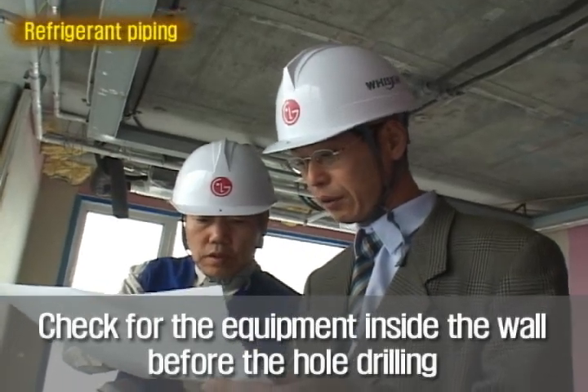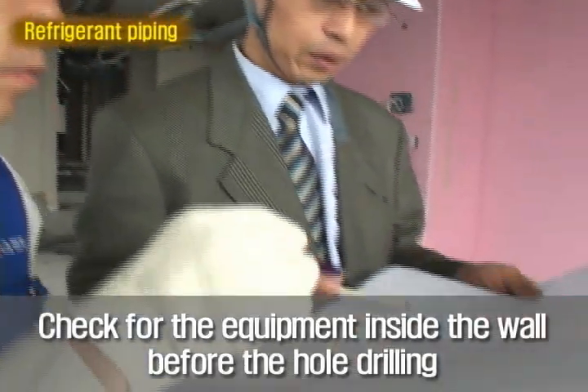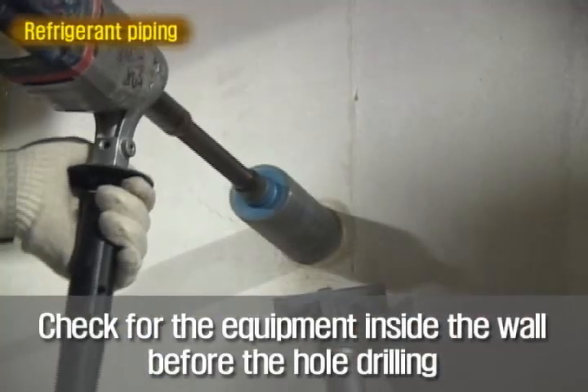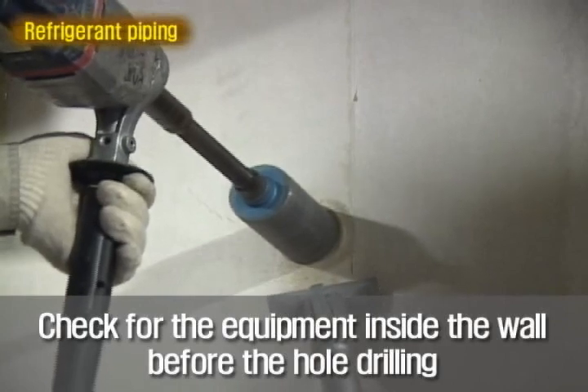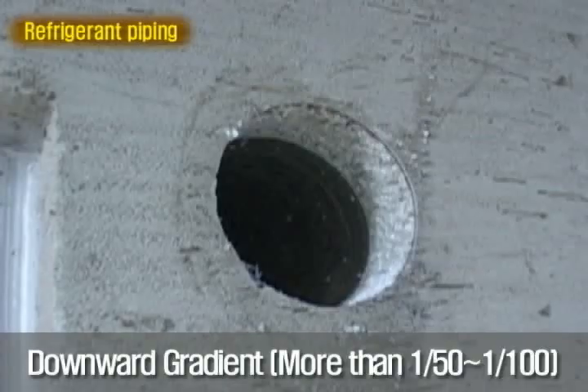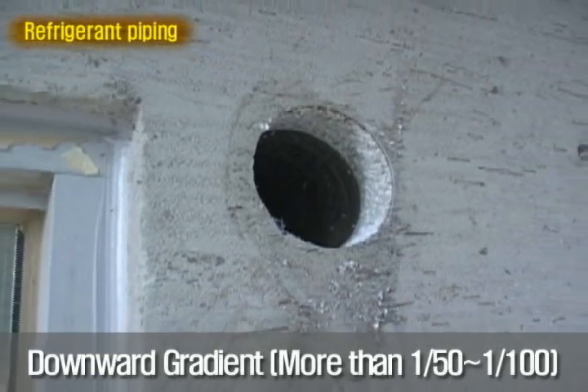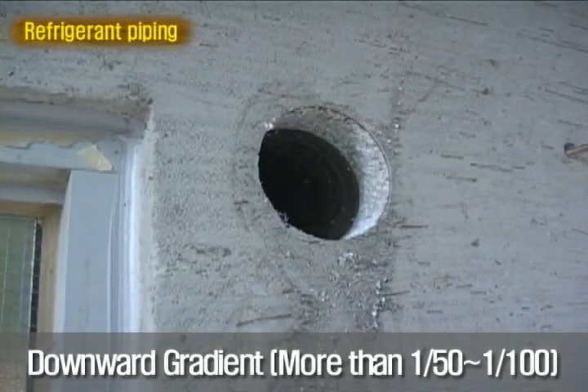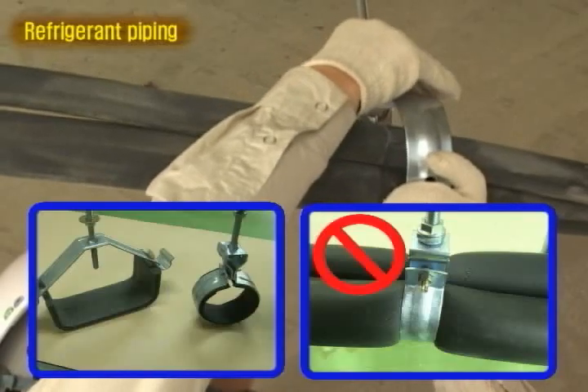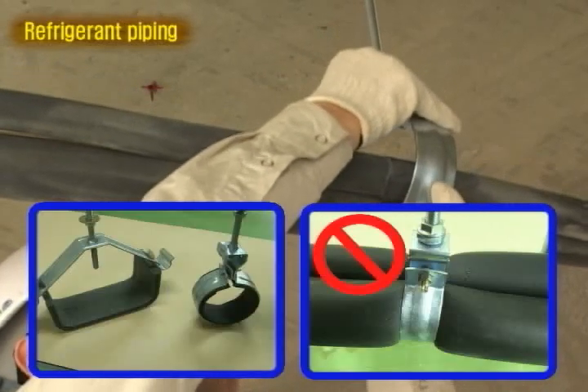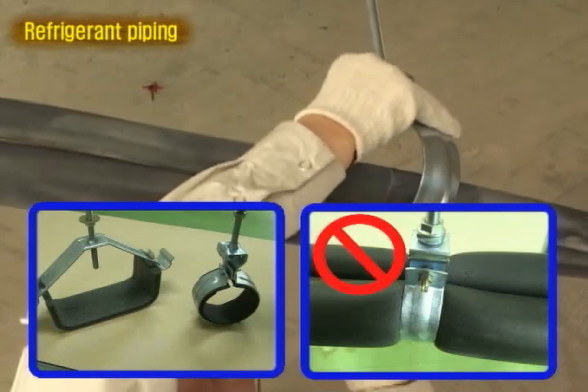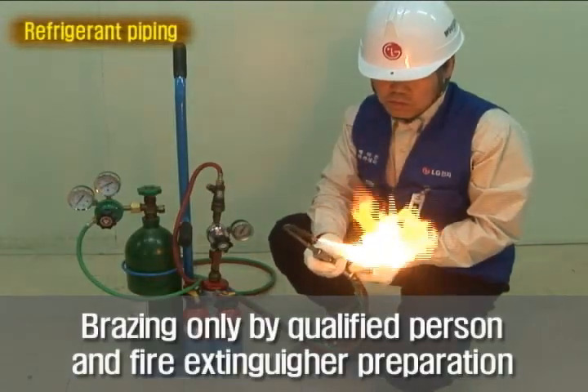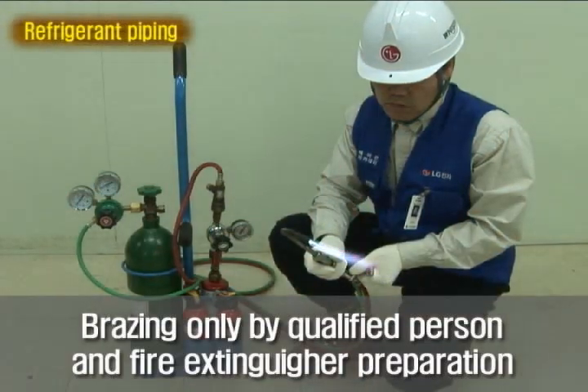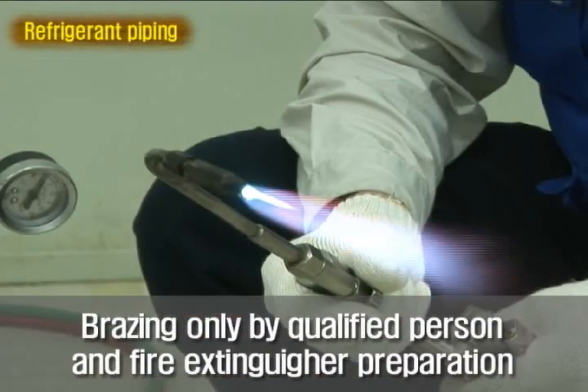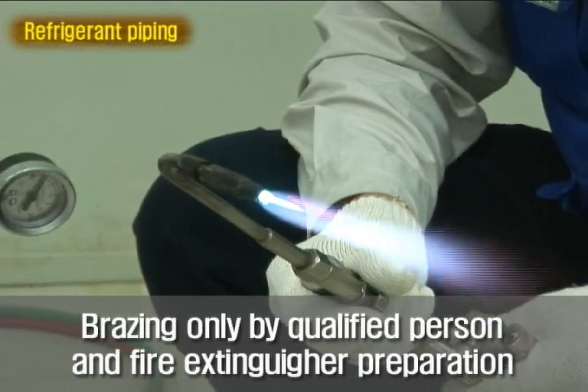Before drilling a hole in the wall, make sure to confirm with the customer if there are any other things inside the wall. While drilling the hole, be careful. To prevent condensation, make sure that the hole has a downward gradient of more than 1/100th. In hanger works, be careful that the insulation is not pressed and crushed. If the piping should be extended with brazing, it should be done by a qualified person only. Prepare a fire extinguisher against a fire.